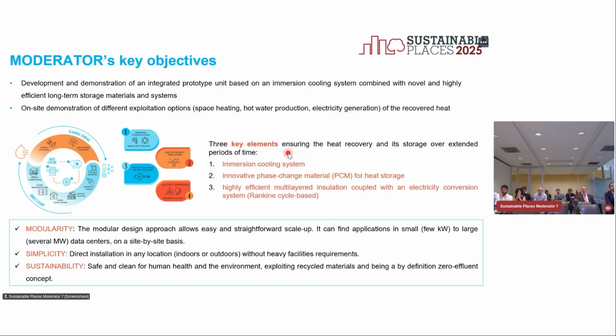To give a quick overview of the moderator project, the way we work with data centers is we focus on the waste heat recovery system. We work with an immersion cooling system, where the goal is to achieve the highest possible temperature without causing thermal degradation of the server racks. We then use this intermittently available waste heat and store it in a newly developed phase change material that I will go deeper into after. The third and last part is setting up the insulation material for this storage system.